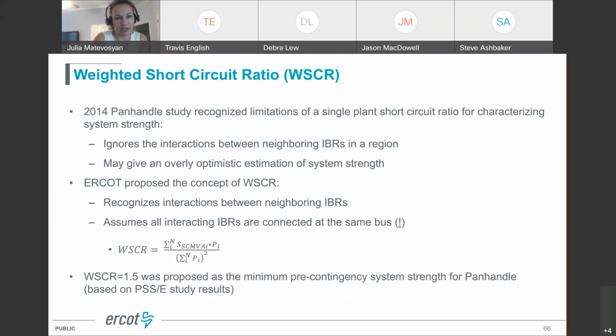So in 2014, upon Panhandle study, we recognized limitations of single plant short circuit ratio in characterizing system strength. As I mentioned, initially we just used short circuit ratio at a given node to try to figure out if there are indications of weak grid conditions or not. But then we realized that in an area such as the Panhandle area, we need to look at nearby inverter-based resources as well. A single short circuit ratio ignores the impact from other inverter-based resources, and so at times it can give you an overly optimistic estimation of system strength.